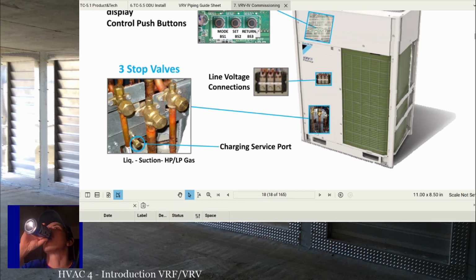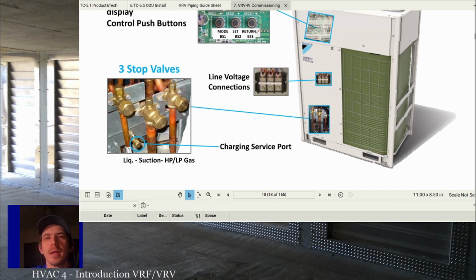Okay. It's one of the less understood aspects about refrigerant piping, and it's something you should be thinking about. Matter of fact, we probably need to go over refrigerant piping some more in a different class, but it's one of the complicated things about refrigerant piping in general. And when you're talking about a large complex system, it gets even more complicated. How do you return oil from 25 indoor units in a system?